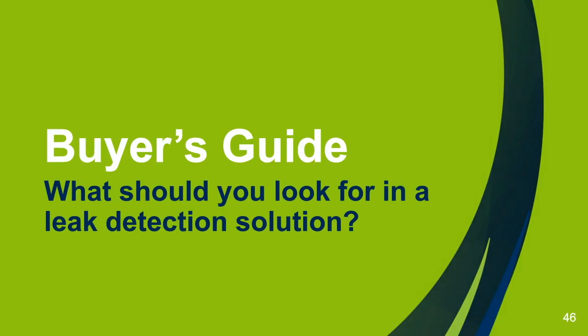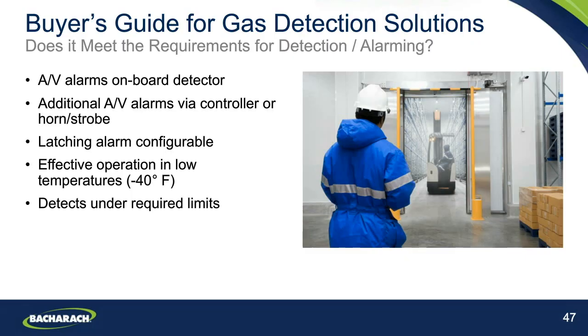So if we summarize what you should look for in a leak detection solution, key questions to ask: does it meet the requirements of the refrigerant safety standards with regards to detection and alarming? Here we want audio-visual alarms on board the gas detector, and the ability to connect to additional audio-visual alarms via a controller or a horn strobe, both inside and outside of the machinery room or the cold room. We want to ensure we can configure the alarm to be latching.